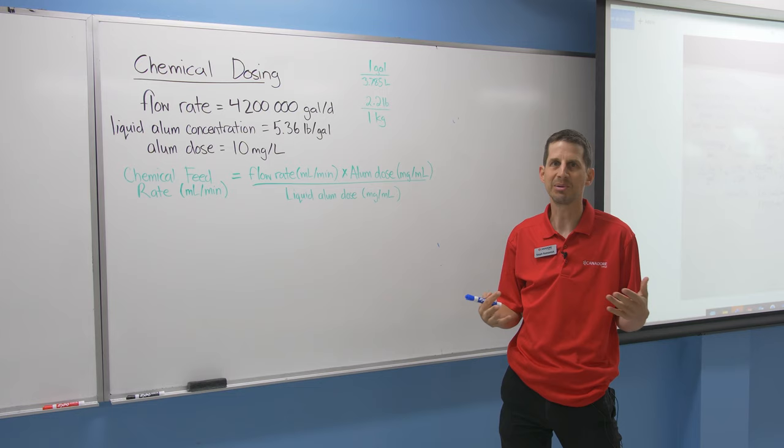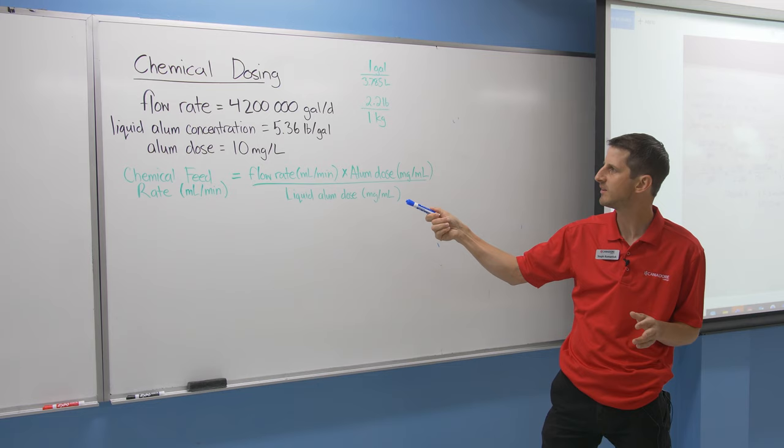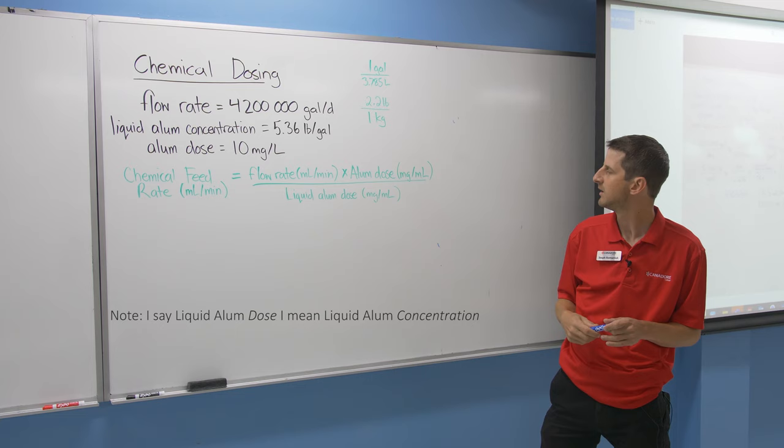As you get more familiar with working in the plant, these numbers will make sense, and other operators can help if you get confused. The formula for chemical feed rate equals flow rate times the dose divided by the liquid alum dose.